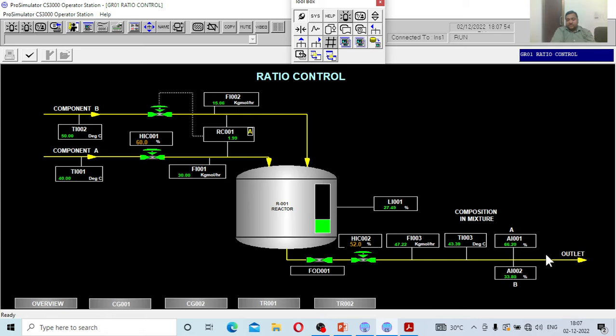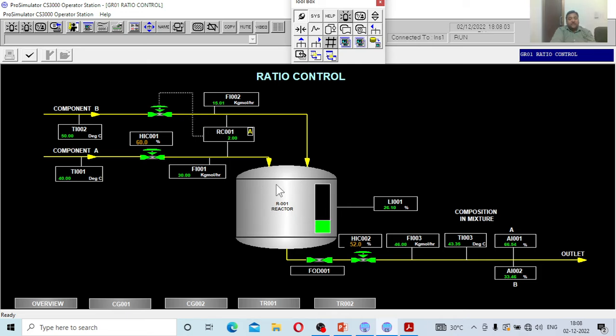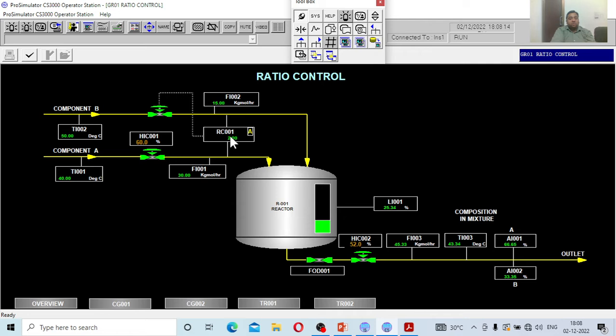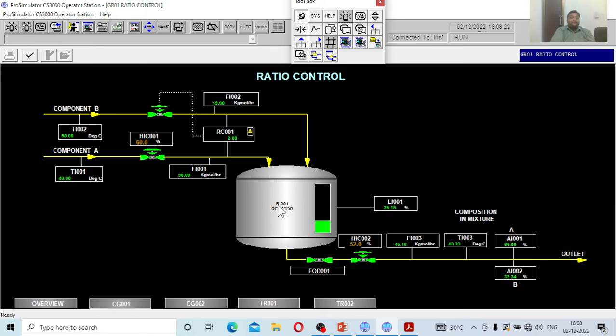See the dynamics. It is very simple, it is a kind of feed forward. Why is it feed forward? Before the reactor gets disturbed, it is taking action before A enters the reactor. Immediately it will sense the change in the flow of A. Accordingly the ratio controller will take action, immediately it will close the valve to maintain the ratio before it enters the reactor. That is why it is called feed forward. Ratio controller is a feed forward controller.